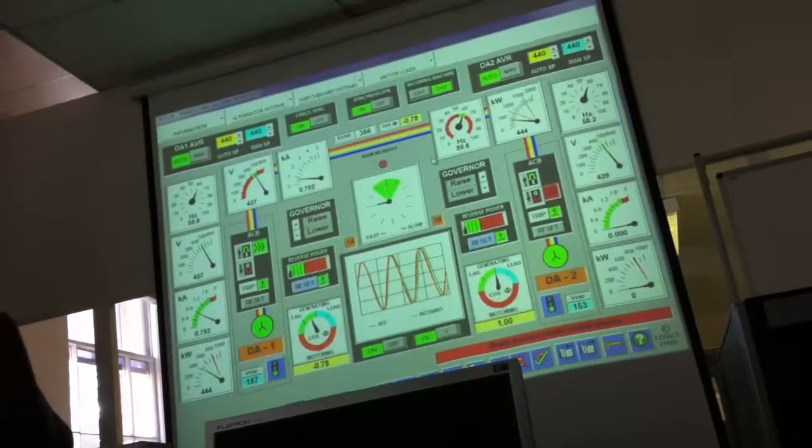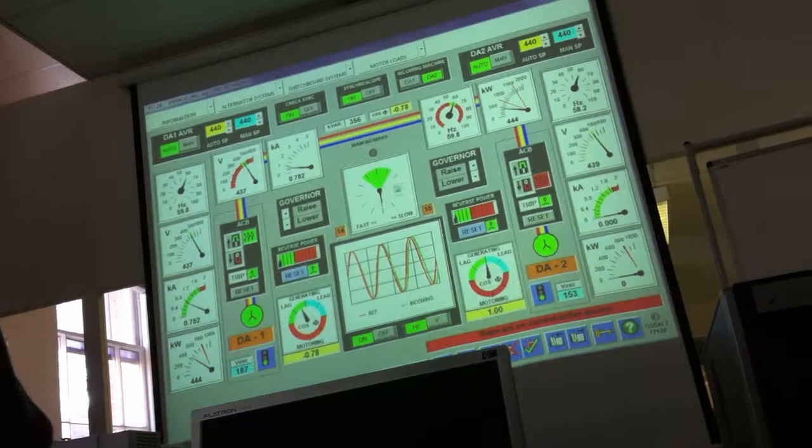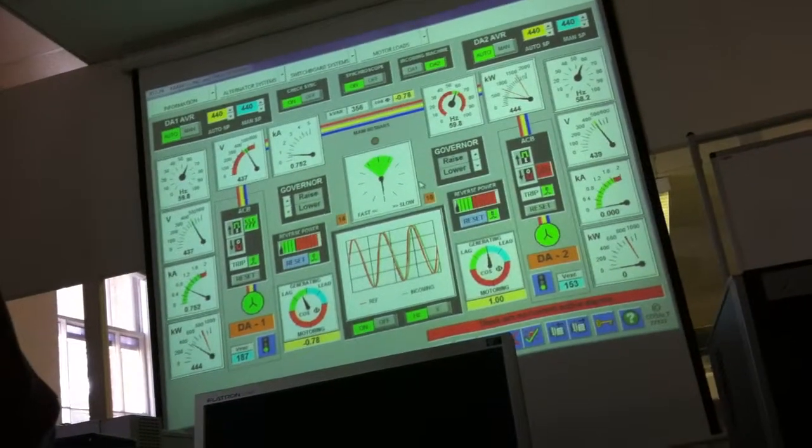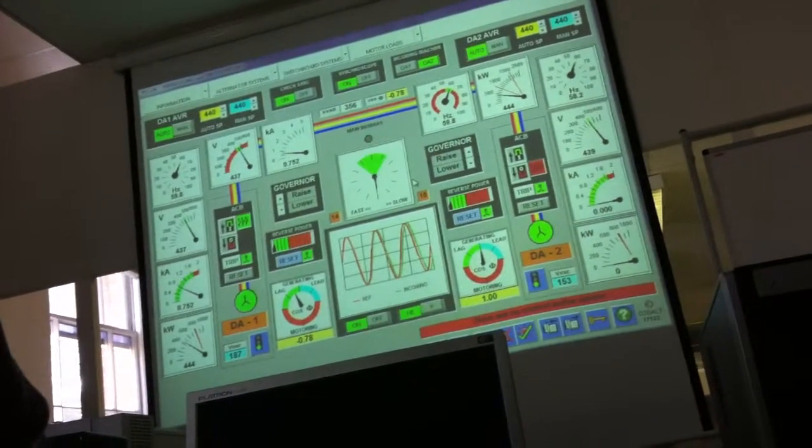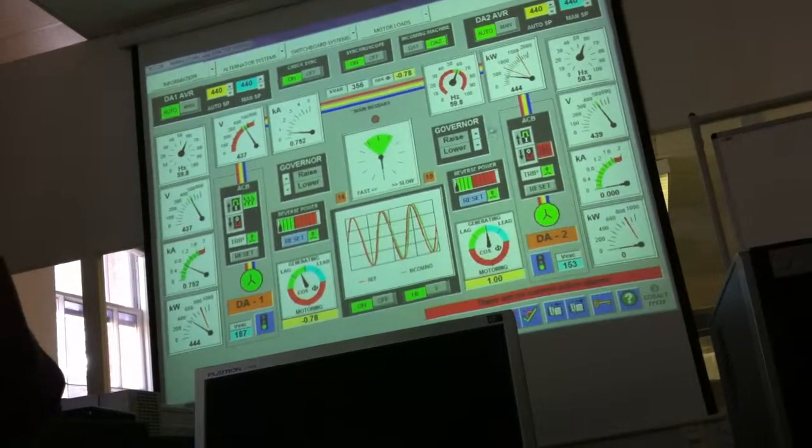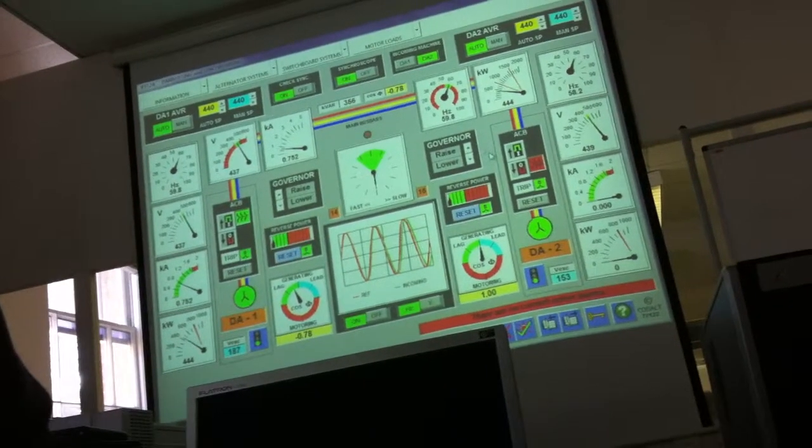Okay with that? Right. So our incoming is anti-clockwise. This signifies that our incoming machine is going too slow. So we are going to bring the incoming machine speed up. By raising the speed, we raise the frequency.